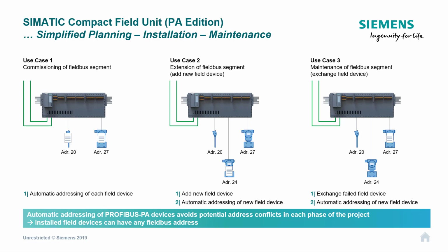So now you have the flexibility of changing your devices. It may even be that you're using an ultrasonic non-contact level sensor and there's vapor in the vessel and you need to change that to a radar. You can do that quite easily with this Compact Field Unit.